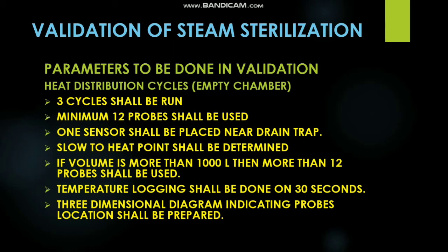If the volume of the steam sterilizer is more than 1000 liters, then more than 12 probes can be used, and these probes shall be placed such that the complete chamber is covered, and 1 probe should be placed near your drain trap. The temperature logging shall be done on a 30 seconds basis.